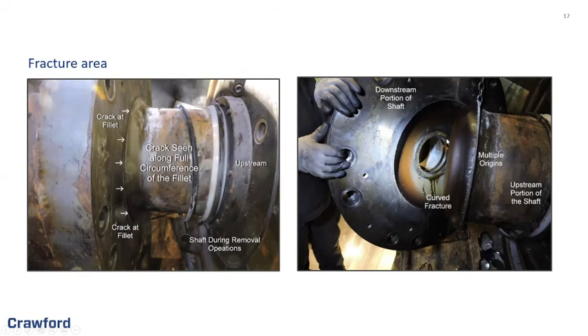You can see here it's come apart as they pulled it out. It was a design issue. So we knew that both the G2 unit, which had failed, and the G1 had the same shaft, the exact same design. So we recommended that the insured replace the shaft in both units in order to prevent a failure on the G1 side.